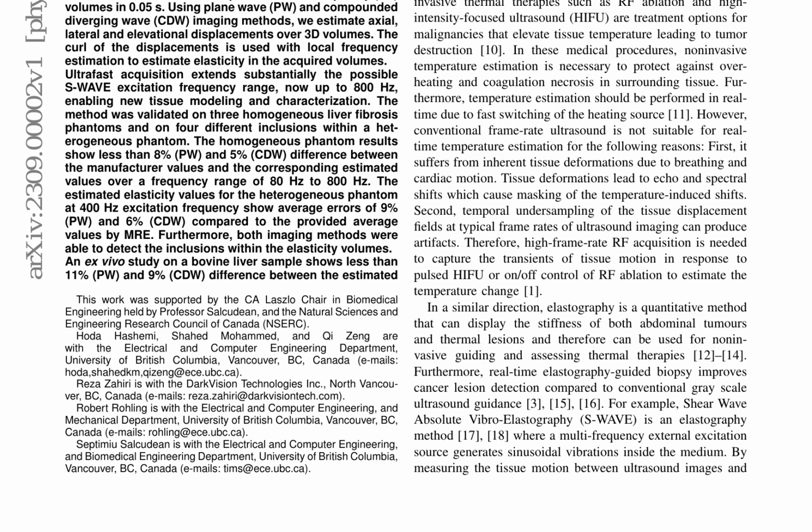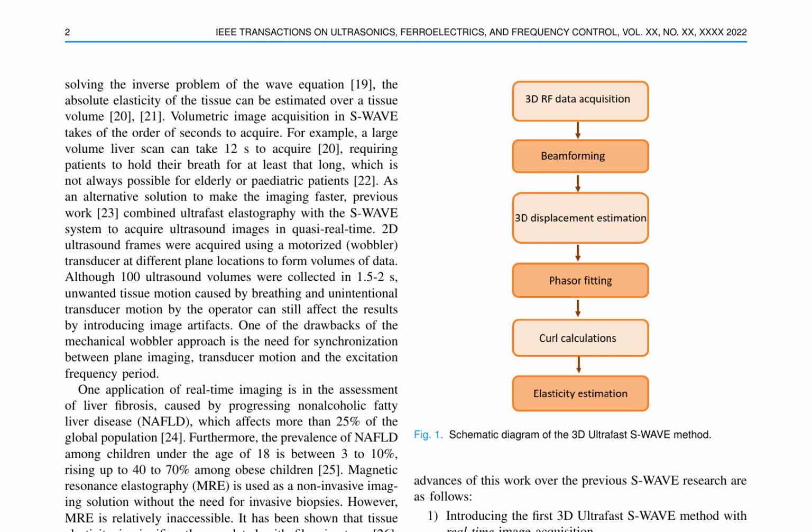An ex vivo study on a bovine liver sample showed less than 11% PW and 9% CDW difference between the estimated elasticity ranges by the proposed method and the elasticity ranges provided by MRE and ARFI. The 3D ultrafast SWAVE method introduces a novel approach to real-time image acquisition for estimating tissue elasticity, utilizing a matrix array transducer.